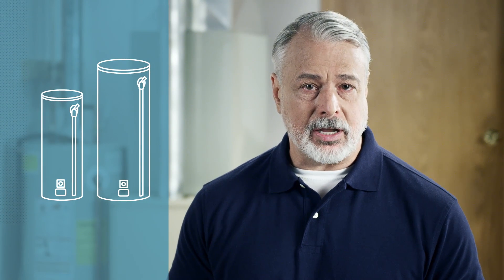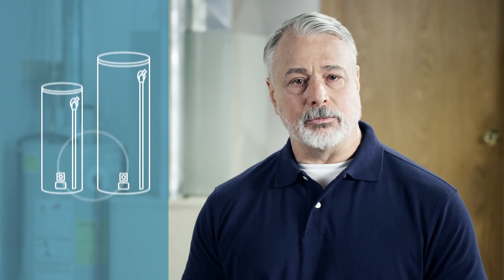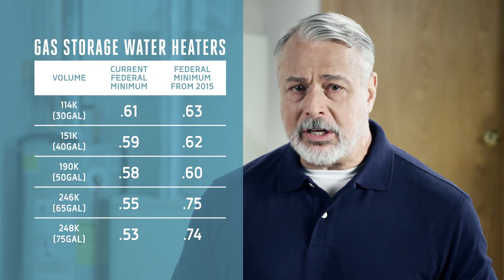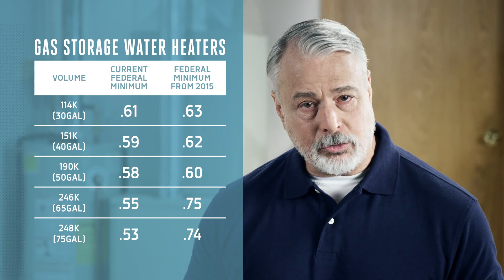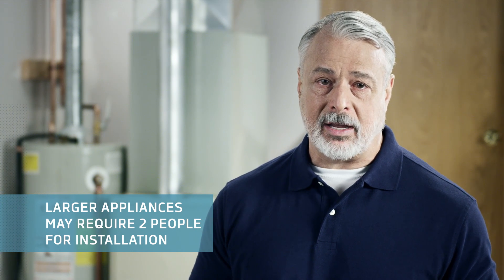So here's what you need to know about this change. First, water heaters are going to get bigger. Gas-powered storage tank models with tanks between 30 and 50 gallons will need additional insulation, which could increase their size 2 inches or more. Tanks larger than 55 gallons will need to be high-efficiency condensing or hybrid electric heat pump units. For these reasons, the new tanks may not fit the current space and the homeowner may have to choose a smaller tank.